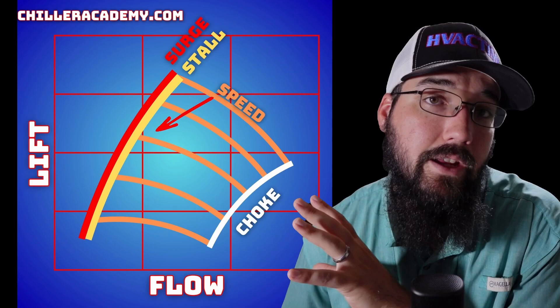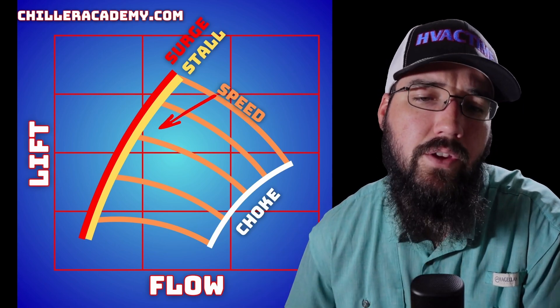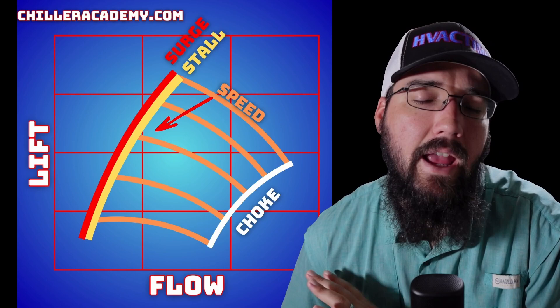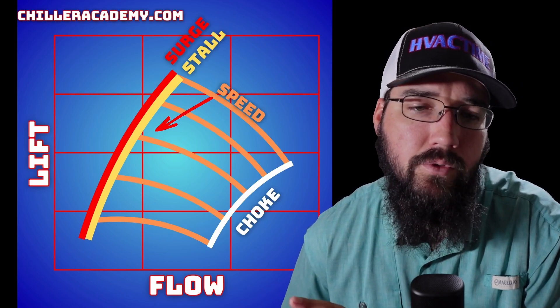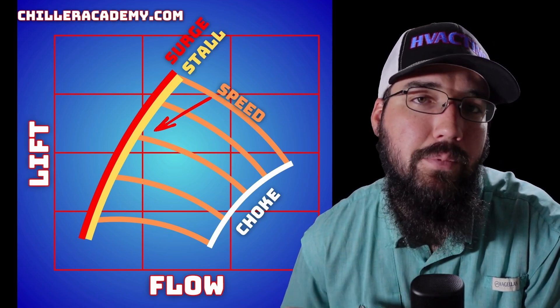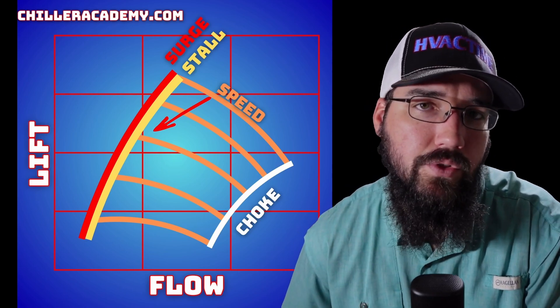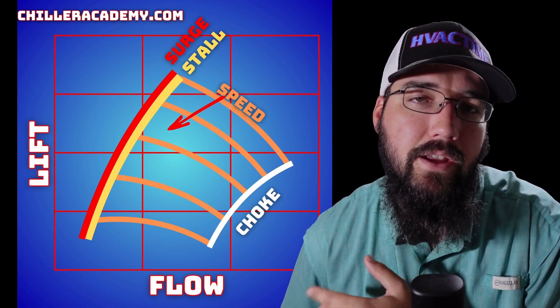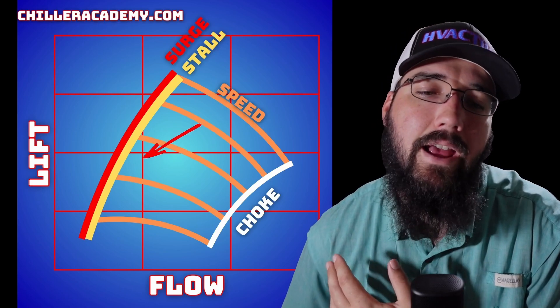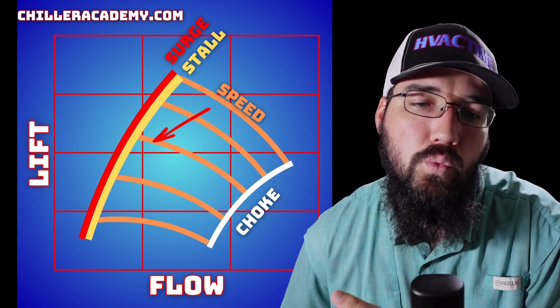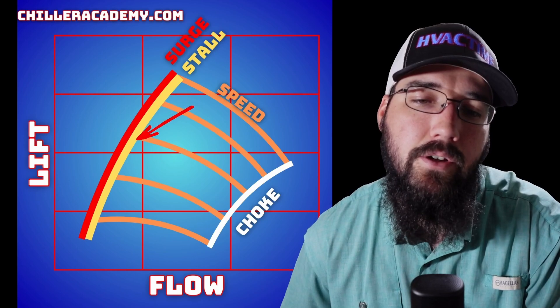Just some things to think about. This is something to ponder on as a concept. Every compressor will have its own graph like this—this is just a general representation of what that graph will resemble and look like. Your control systems have a graph like this programmed into them that, as it's controlling the staging and loading of the compressor, it knows where it's at in relation to these lines.